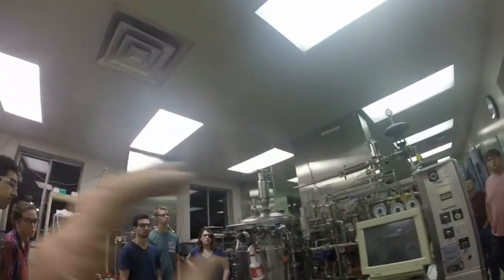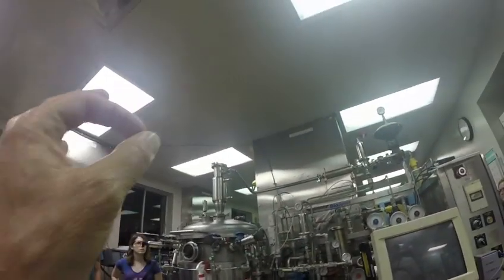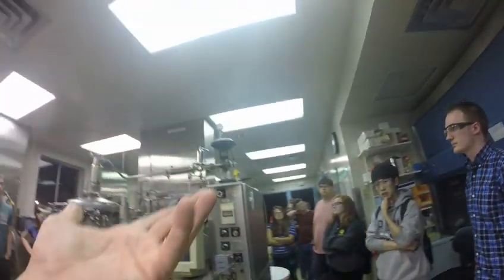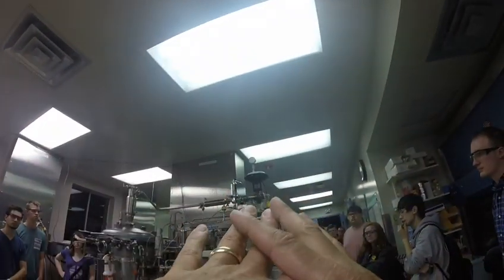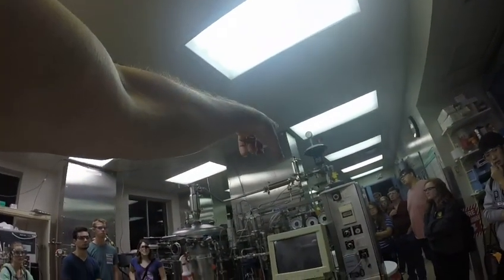Okay, so it turns out it's there to prevent clogging, but for an entirely different reason. What would be your biggest risk if you have a 0.2 micron filter that no longer can pass gas through it? Pressure buildup. It would be water. If I have any water get onto something with pores that small, surface tension will make it virtually impossible to push any liquid or any gas through the actual sterilization filter.